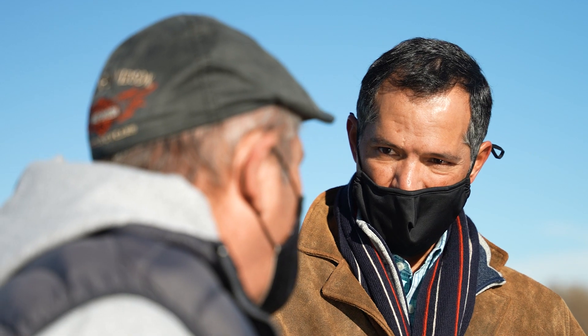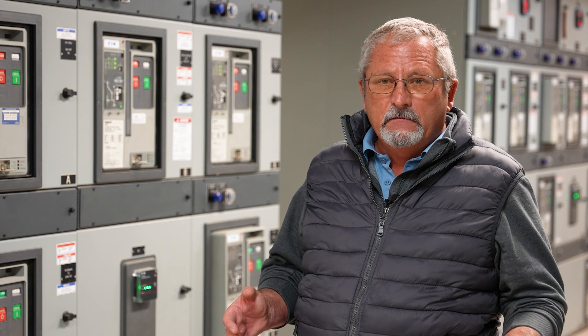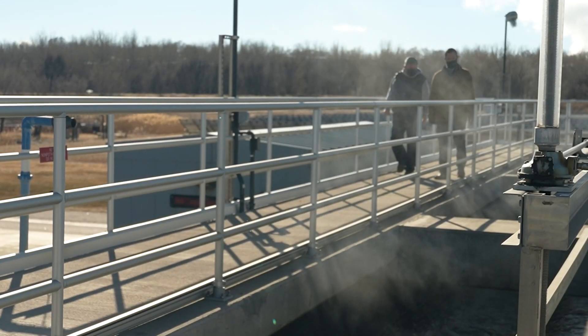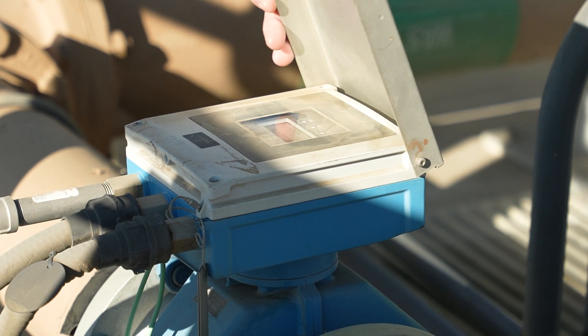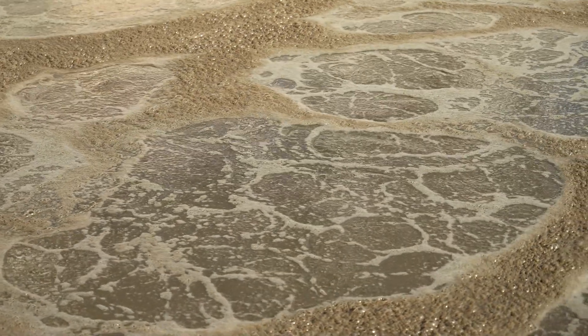As we were developing the plant, we were looking at how we can be self-sufficient, and that's when AVN and the hydrocyclones came along. We do have the ability to feed chemicals, but our goal is not to. At Pueblo, for advanced aeration control, we use AVN control, which maximizes nutrient removal by using the influent carbon as well as reducing energy for aeration. For selective wasting, we use hydrocyclones, which retain microorganisms that are favorable for BNR, as well as selective wasting, which promotes settling performance of activated sludge.